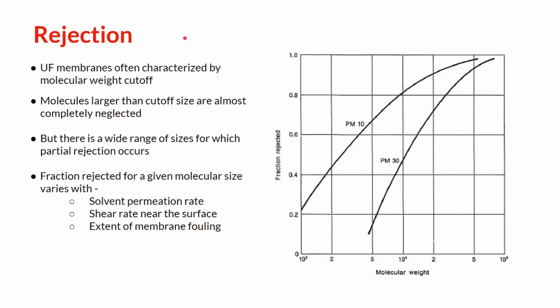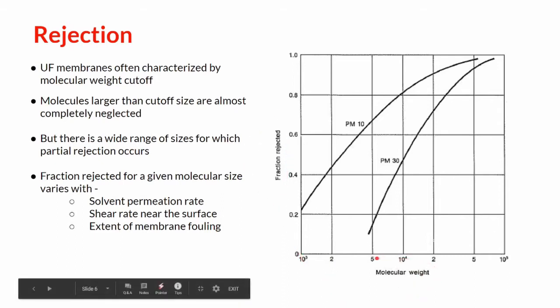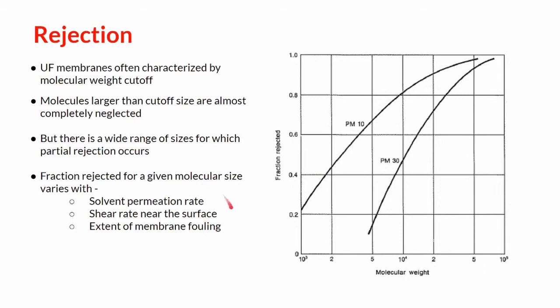Rejection is an important phenomena for ultrafiltration membranes as the ultrafiltration membrane tends to reject particles based on the molecular weight. Molecules larger than the cutoff size are almost completely rejected. The graph on the right shows the fraction rejected with the molecular weight for PM 10 and PM 30. This has been taken from a research paper. Word of caution: these data might vary from case to case as the fraction rejected for a given molecular size varies with solvent permeation rate, shear rate near the surface, and the extent of membrane fouling.